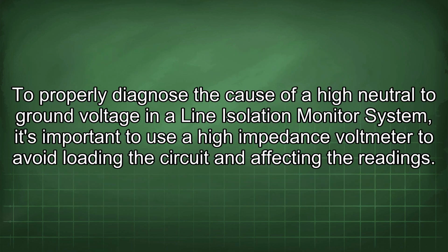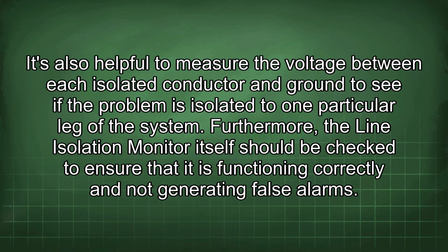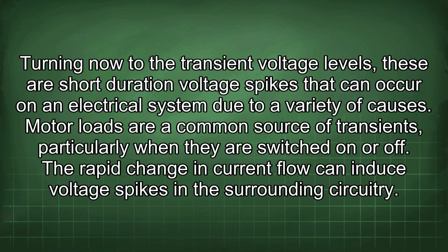To properly diagnose the cause of a high neutral to ground voltage in a line isolation monitor system, it's important to use a high impedance voltmeter to avoid loading the circuit and affecting the readings. It's also helpful to measure the voltage between each isolated conductor and ground to see if the problem is isolated to one particular leg of the system. Furthermore, the line isolation monitor itself should be checked to ensure that it is functioning correctly and not generating false alarms. Turning now to the transient voltage levels, these are short-duration voltage spikes that can occur on an electrical system due to a variety of causes.